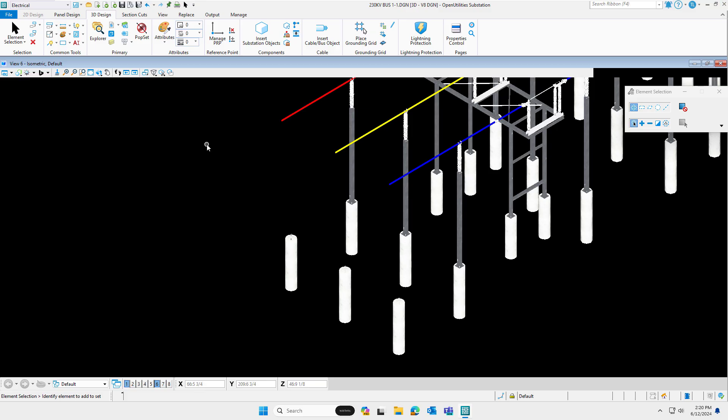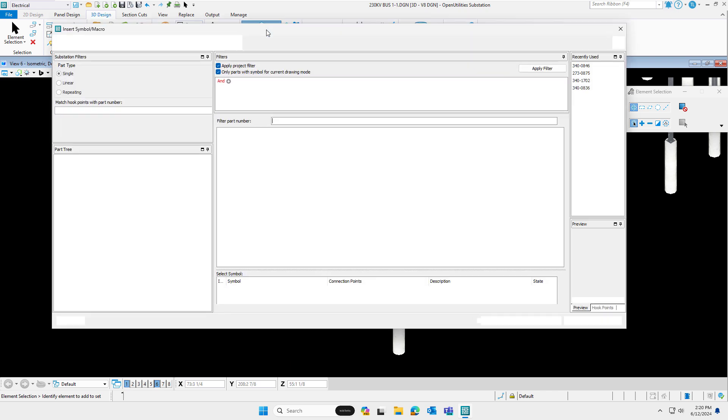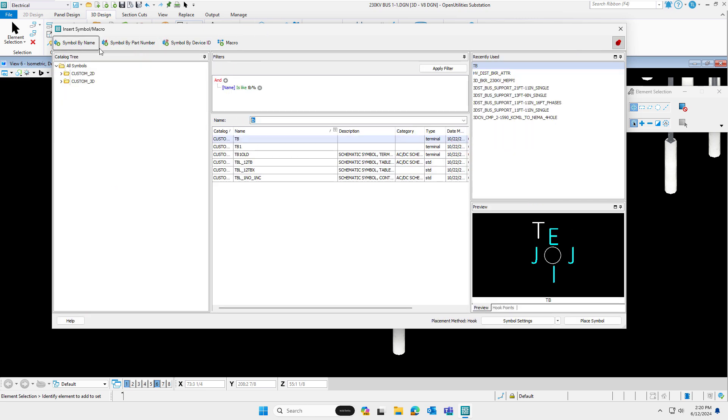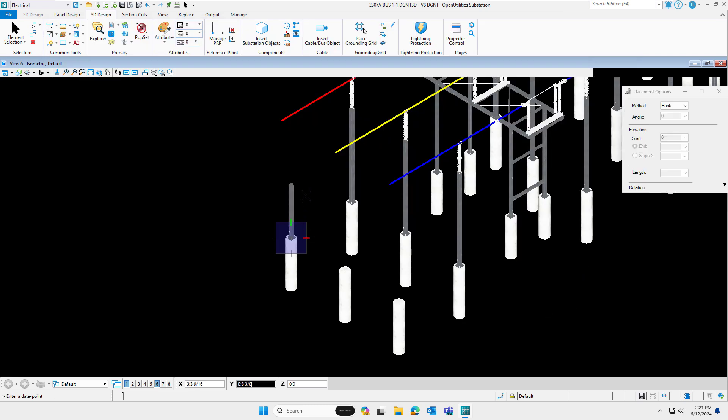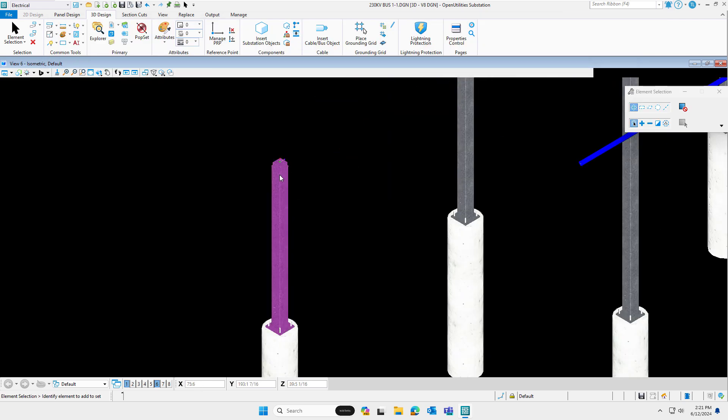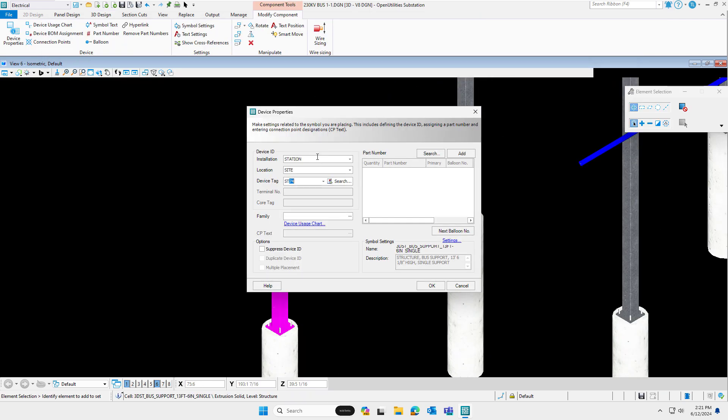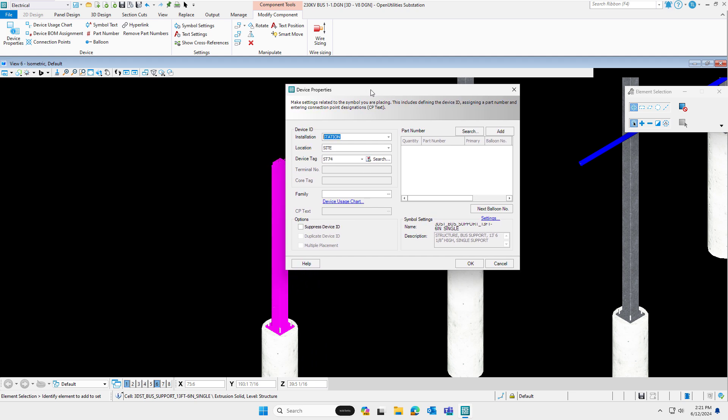Let's take a look at this feature in action. Earlier, I imported custom parts from an Excel file. In my case, I was importing some bus supports. I insert a new 3D symbol for a bus support. And then I want to tie that symbol to that imported item, which is already on my bill of material. So first I'm going to go ahead and find the symbol to place in my 3D model. In this case, I'm using a symbol by name. I'm going to pick one of the single ones here. I'm going to go ahead and place that down. And you can see that I've placed that bus support down. I'm going to take a look at its device properties. As most of you are aware, the equipment tag or the full equipment tag or device ID is a combination of installation, location, and device tag. This is to take note because when we imported the custom parts, some of those I actually imported the equipment tag. So that's going to become an important factor when I actually link that item from my bill of material to this object in my model.